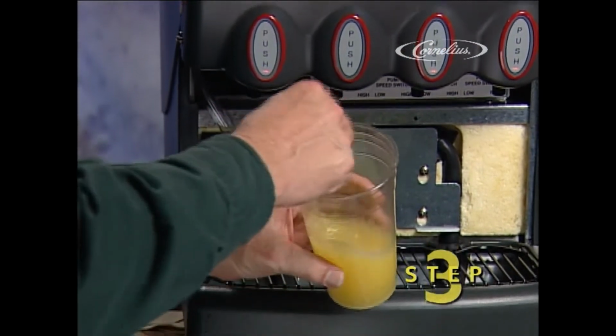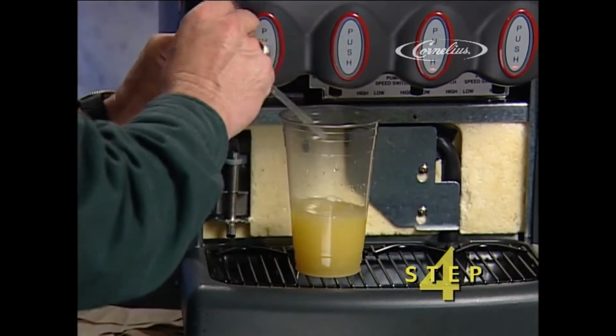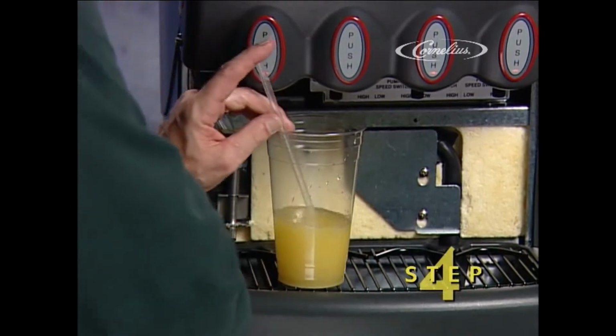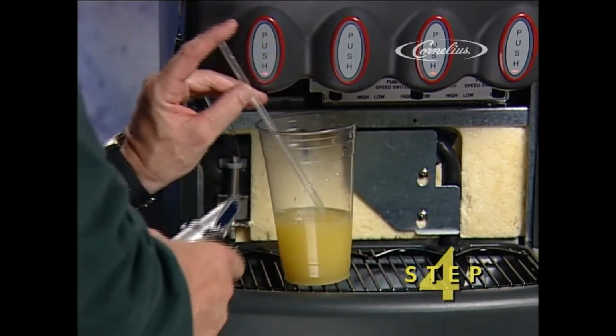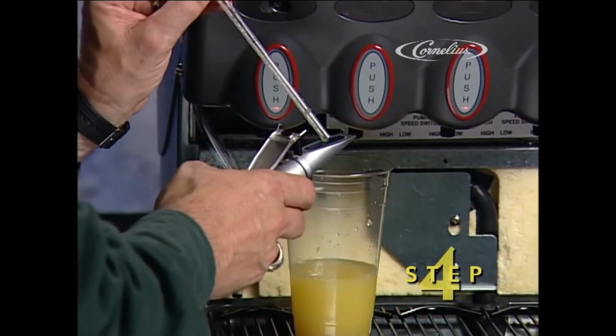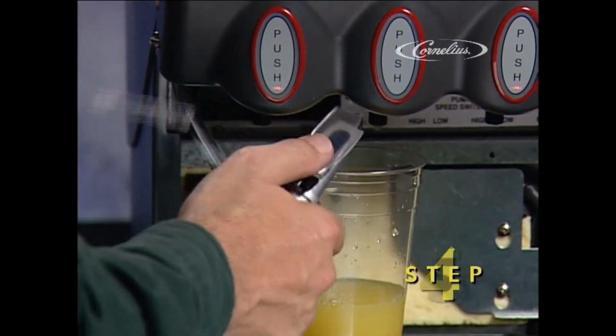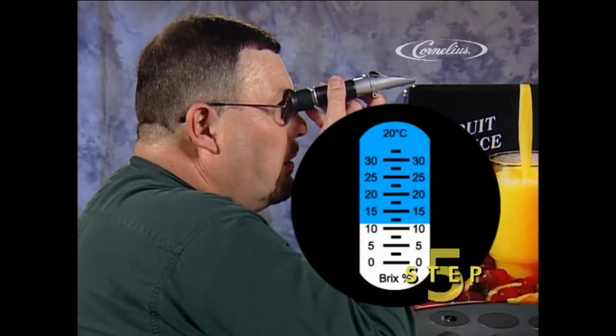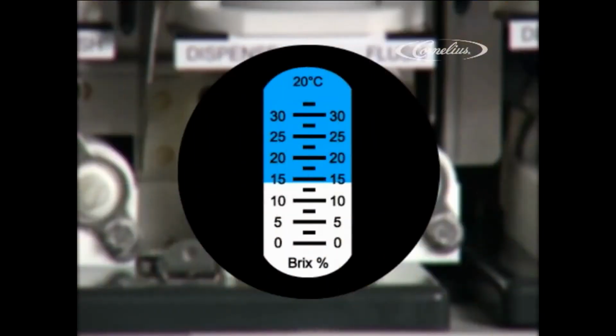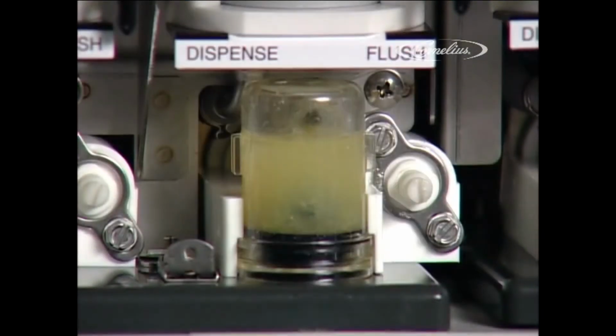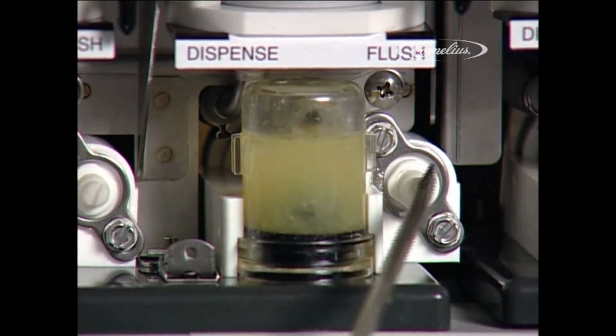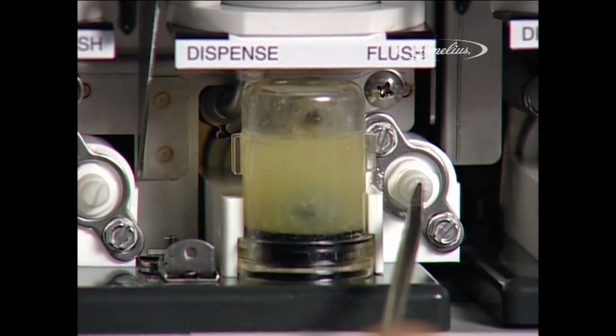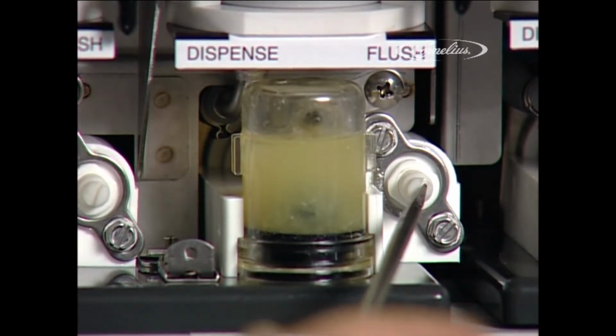Make sure you stir it once or twice, then place a clean straw in the middle of the sample and with your middle finger over the top of it, draw a sample from the cup. Take that sample and put it on the glass or prism of the refractometer. Close the lid and look at the Brix reading inside. If, for example, the Brix reading is high at 14, there is too much concentrate and more water is needed. To make that adjustment, take the flat blade screwdriver and imagine that the flow control is the face of a clock. If you are at 14, turn the dial precisely 3 minutes clockwise.